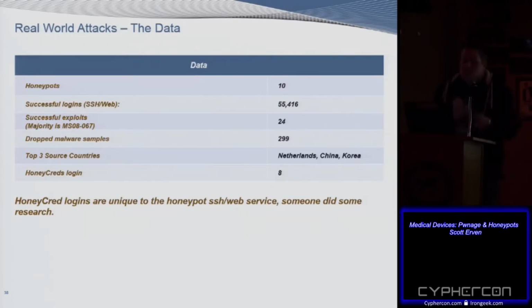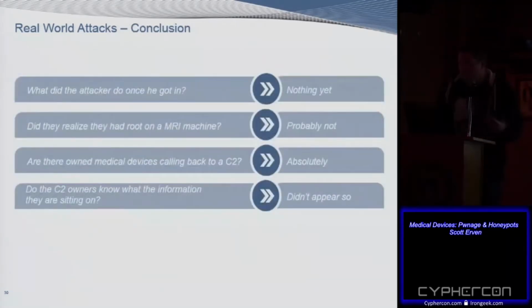Honeycreds logins, this was unique to each system. So we set up Honeycred logins for each system, for each IP, and we dumped them to Pastebin and Twitter to see if people would scrape them and then log into our medical devices that are wide open for attack. That happened 8 times. So what did we see when they got it? We actually didn't see anything. We didn't see any indication that they knew they were on a medical device, that they didn't know they were just on some other Linux system or XP system.